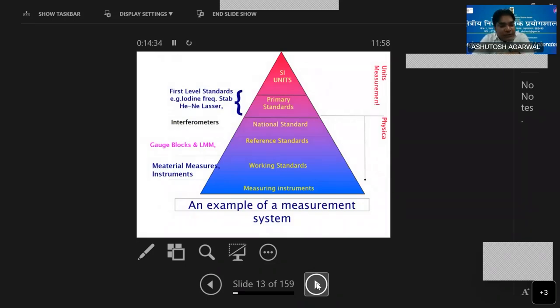So we have the SI unit. To realize that SI unit, we have the primary standard. Our primary is the iodine stabilized helium neon laser, and soon, maybe next year, we are going to replace it with the optical frequency comb. Then we have two interferometers: the gauge block interferometer and the length measuring interferometer. These two are our primary, secondary sources. Using those two interferometers, we calibrate our gauge blocks by the gauge block interferometer and the LMM by the laser interferometer.